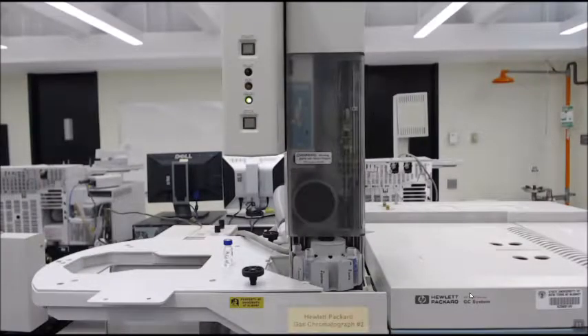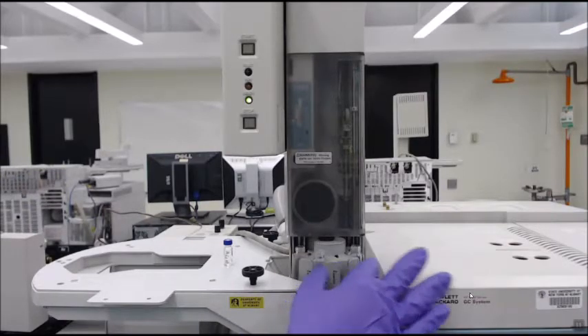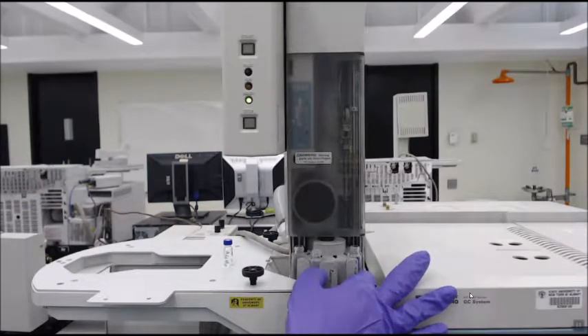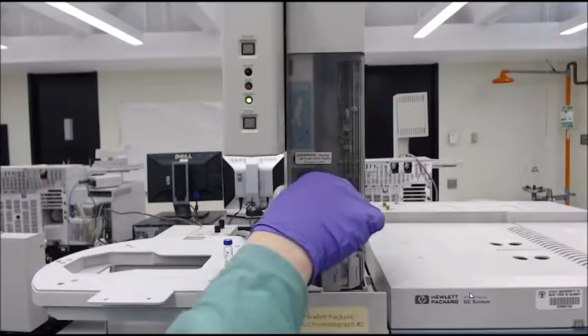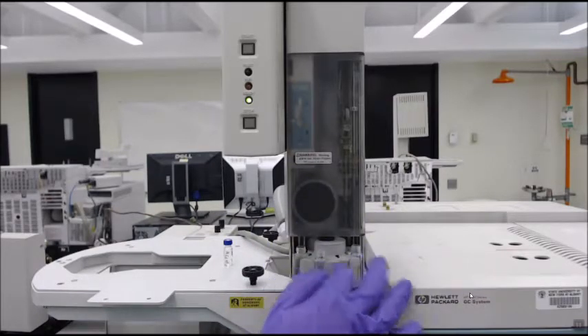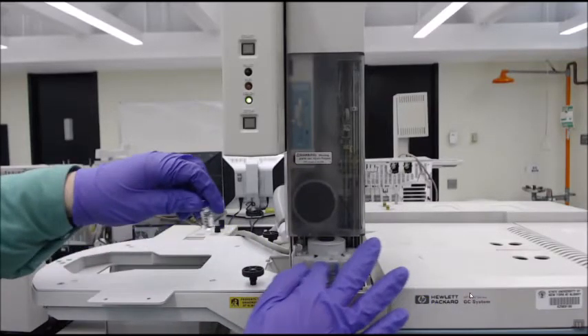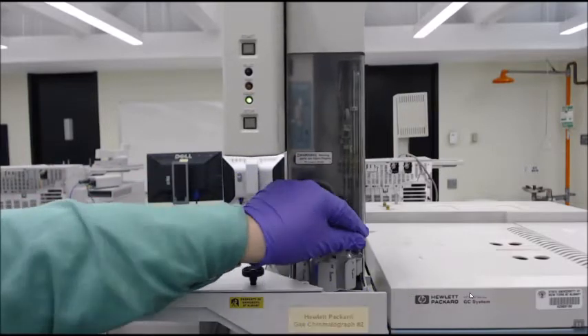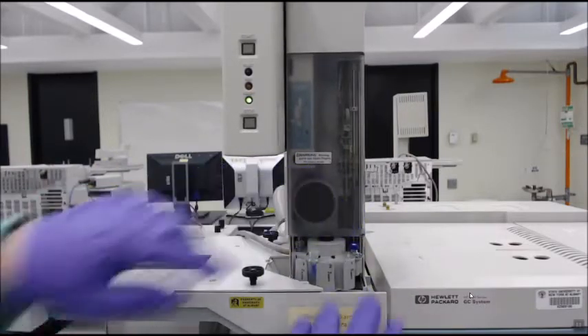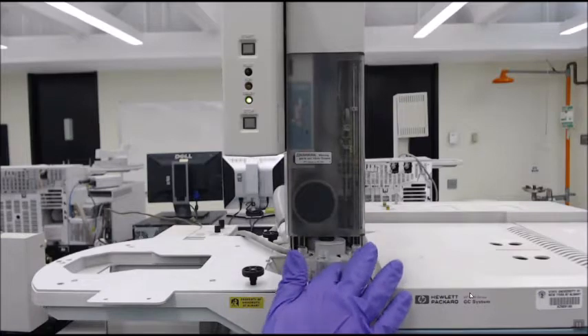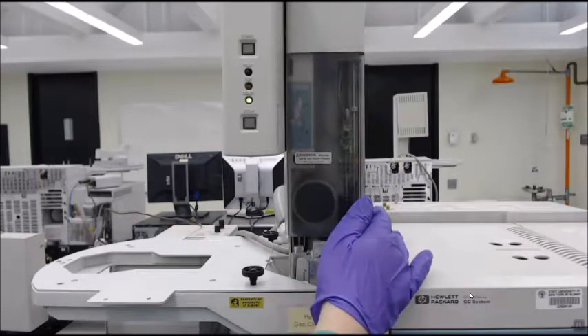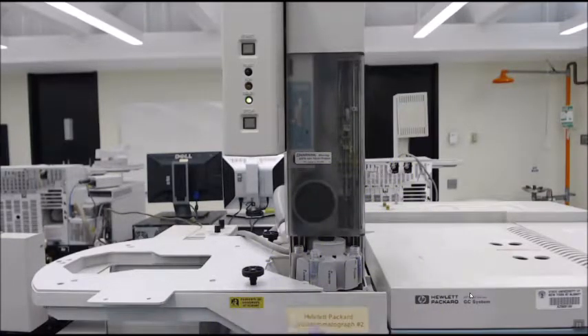So before we set up our method, we need to load our sample. To begin with, we make sure that the waste vials are present. I filled solvent A with acetone. Then I load my sample into the sample slot. The purpose for all this is that we need to wash the needle first with solvent and then with our sample before we inject. I will demonstrate that now.